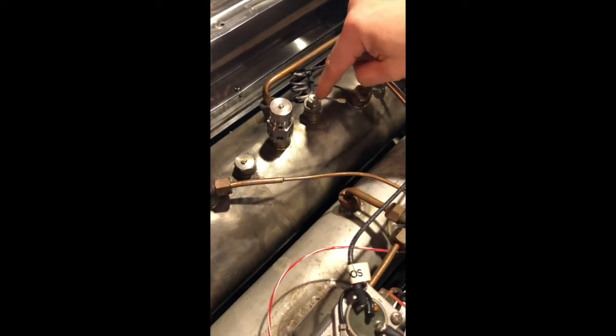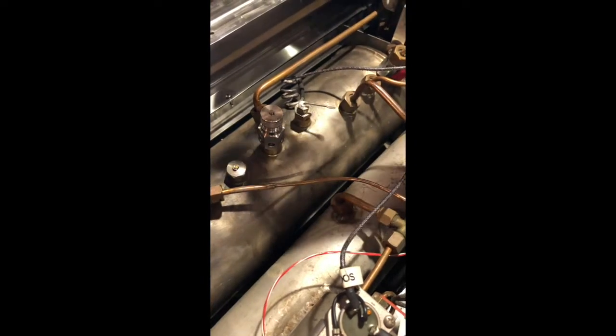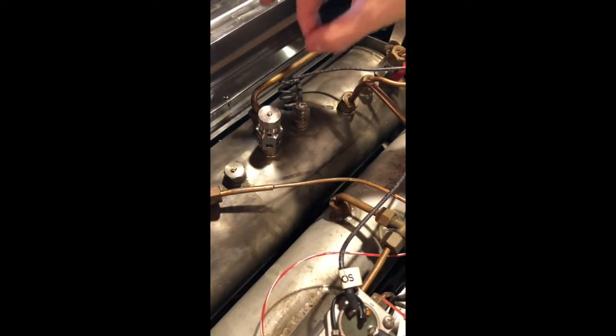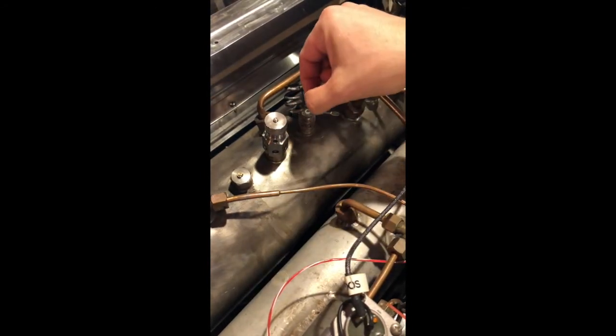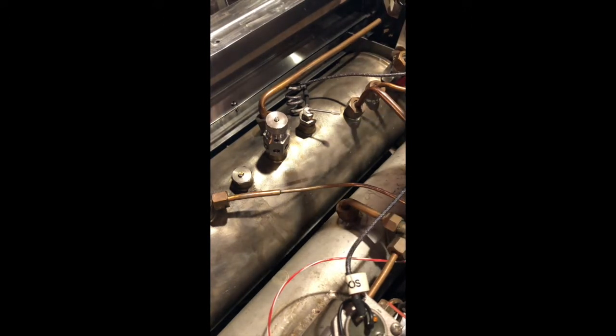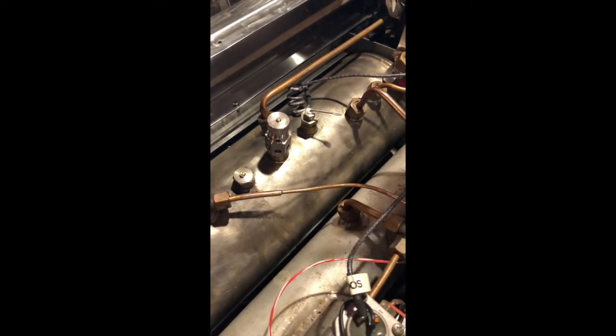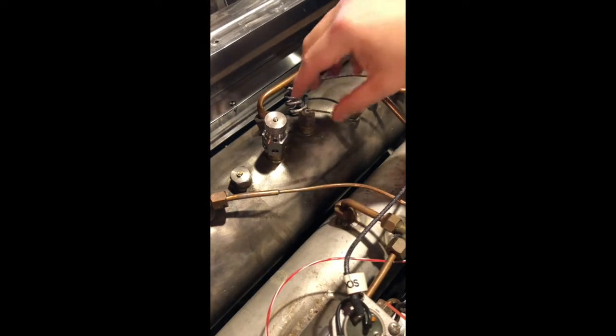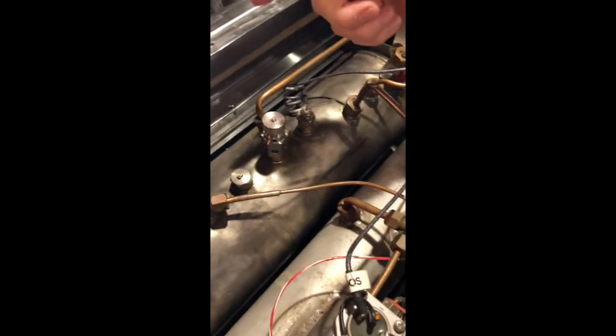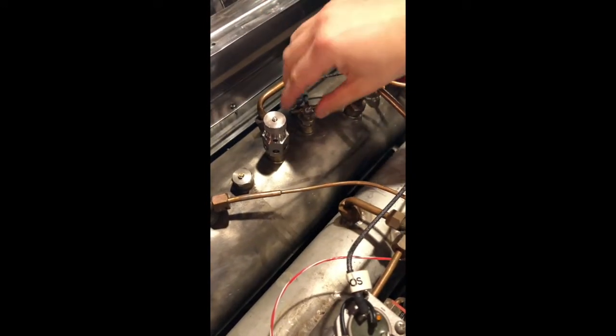When this comes new, it's actually straight up and down, and then once we set the level in the boiler to what you want it to be, if the probe's lower, there's going to be less water in the boiler. If the probe's up higher, the water's going to be able to fill up higher. As soon as the water touches the probe, that activates and closes the switch and makes it stop filling up.